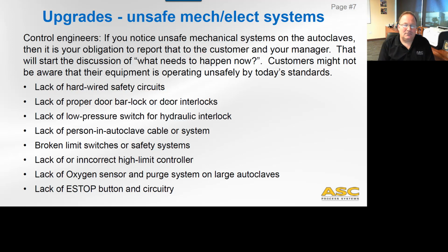So what are the things that you want to look for? Lack of hardwired safety circuits is a good one. Lack of proper door bar locks. There are some autoclaves out there with very poor door lock interfaces, and it makes them dangerous pieces of equipment. A lack of a low pressure switch to indicate that the pressure in the autoclave is at zero before turning on the hydraulics, for example. Lack of person-in-autoclave cabling systems, what we call the safety cable system. Broken limit switches on certain safety components, lack of or incorrect high limit controllers, lack of oxygen sensor and purge systems on larger autoclaves is also a big one, because a lot of older autoclaves that were large don't have those very standard safety systems, okay? And lack of an e-stop button and circuitry, which you'll find on many autoclaves.